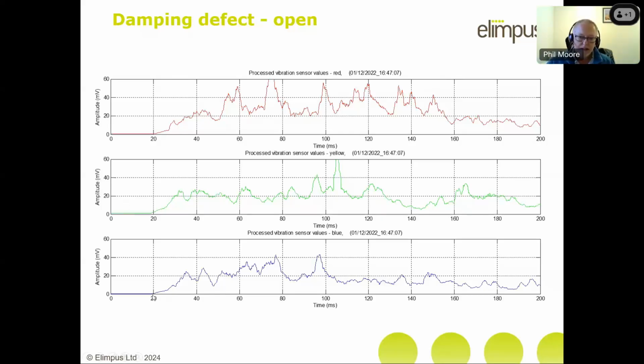And you can see here that the breaker is instructed to open at around 18 milliseconds or so, and you get this ramp up in the vibration energy. This is the contacts accelerating, and it plateaus out. You can see that on the yellow and the blue, on the red, and then around about this position here, say 45 milliseconds, the contacts are more or less at their maximum separation.